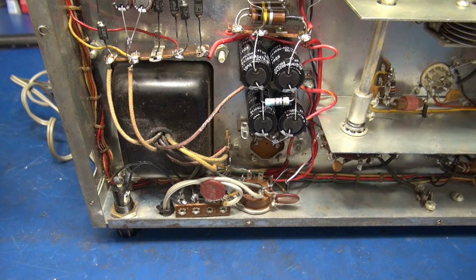Improvement number 1, AC line fusing. Normally there would be a little glass circuit breaker sitting here on this terminal board. Those circuit breakers are known for failing, and therefore you lose protection for your power transformer. So I'd highly suggest that you add a chassis mount fuse holder and install a 3AG 3 amp fuse. You simply swing the wires back over where that circuit breaker used to be.